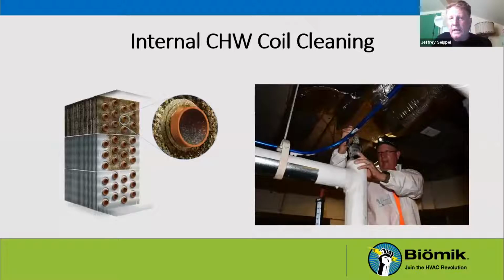A new aspect of our development is cleaning of internal aspects of a chilled water coil. So those tubes that you see is what the chilled water flows through. The aluminum fins then are what the air that the building has flows over. So we're successfully treating the air side of the coil with our other process. What we found is that there's just as much problems on the chilled water side.